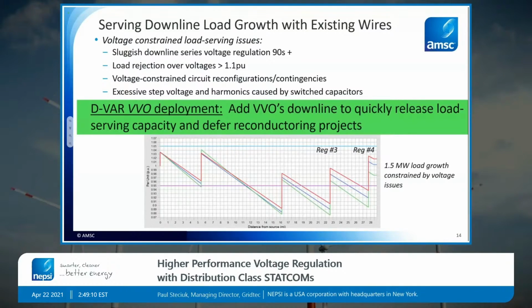When a sudden load were to drop, all of those voltage regulators are ramped up. And right after that load trips off, you can get very high voltages, which can prevent the ability to serve this load growth towards the end of the feeder. Other problems are during reconfiguration. Utilities build their system to be backed up by other feeders. And when that system has to get backed up, series regulators are not the ideal way to accommodate that power flow coming in a reverse direction now.